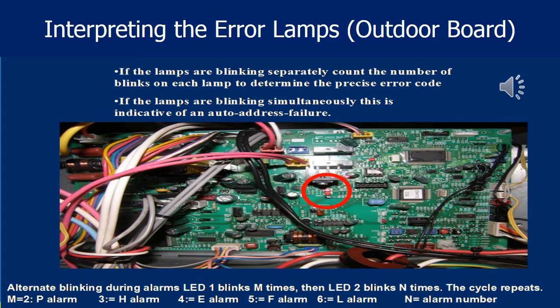As mentioned earlier, error codes can be displayed from either the indoor unit's wired remote controller, at the indoor unit's receiver lamp assembly when a wireless remote controller is utilized, or through LEDs 1 and 2 on the outdoor unit's main control board. LEDs 1 and 2 should be completely off when the system is operating without any error codes. When the LEDs 1 and 2 located on the outdoor unit's main control board are blinking or on solid, they represent an error code has occurred. When the 2 lamps are blinking simultaneously, an auto address failure has occurred. The exact error code can be shown by the number of times each lamp blinks.